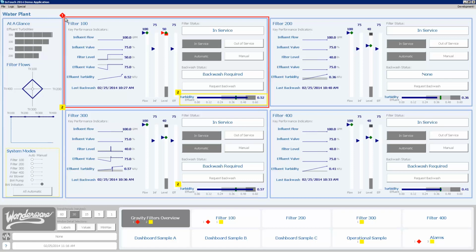At each level within the system, that goes down to the individual variable, which is known as an attribute, or at the higher level, the equipment level, what we call an object, or even at multiple levels of equipment, what we call areas, I'll be able to have numeric values of the distribution of the alarms by severity. It's being used in this particular example to place these badges on the navigation buttons.